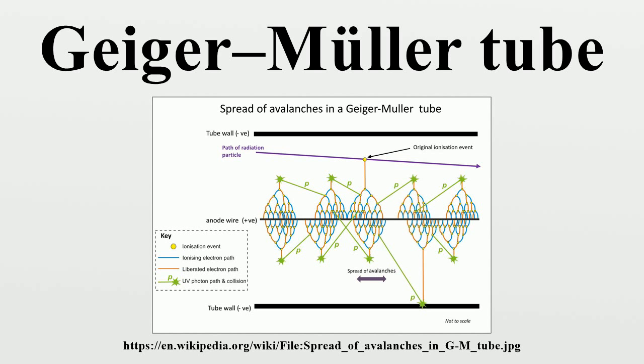Energy compensation. If a GM tube is to be used for gamma or X-ray dosimetry measurements, the energy of incident radiation, which affects the ionizing effect, must be taken into account. However, individual pulses from a GM tube do not carry any energy information. A solution is to assign a radiation dose to each counting event, so the tube characteristic relates the number of counts to the intensity of incident radiation.